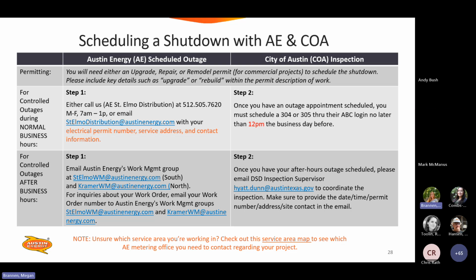Alrighty. Scheduling a shutdown. So here we are with Austin Energy scheduled outages and City of Austin inspections. You will need both to schedule these shutdowns. So just keep in mind there's a step 1 and step 2 for either controlled outages during normal business hours or after business hours. There's a slightly separate process there. Keep in mind you'll need an upgrade, repair, or remodel permit that is active first to schedule that shutdown, and then include any key details in that permit, such as upgrade or rebuild, within the description of work.